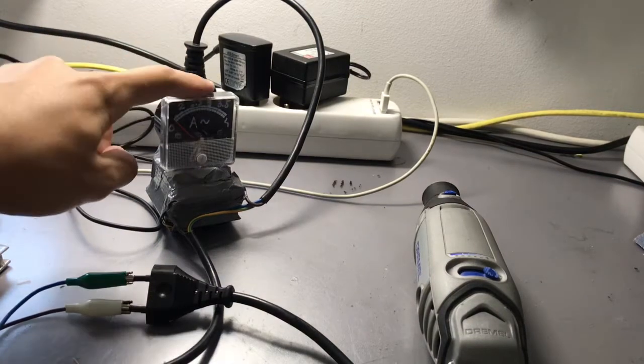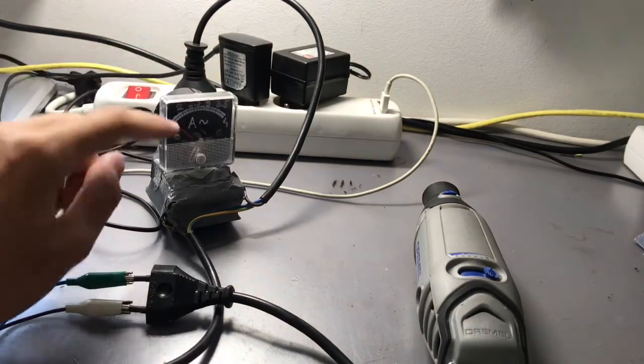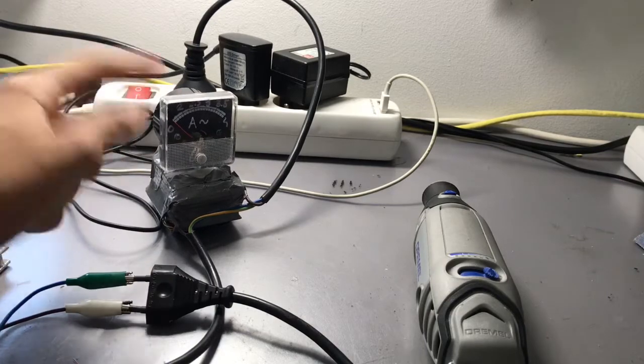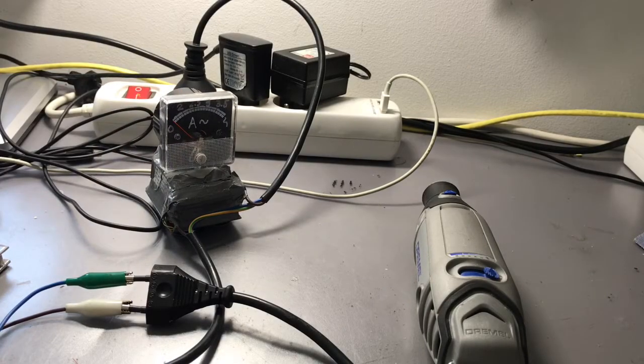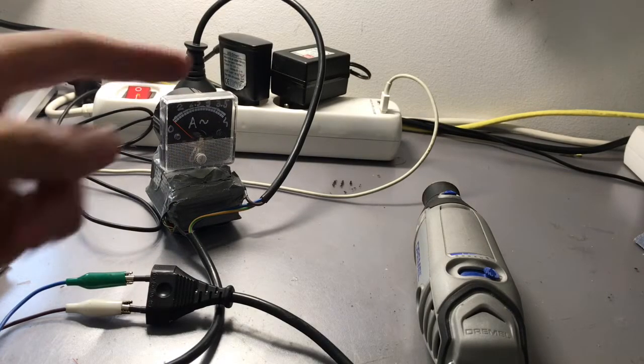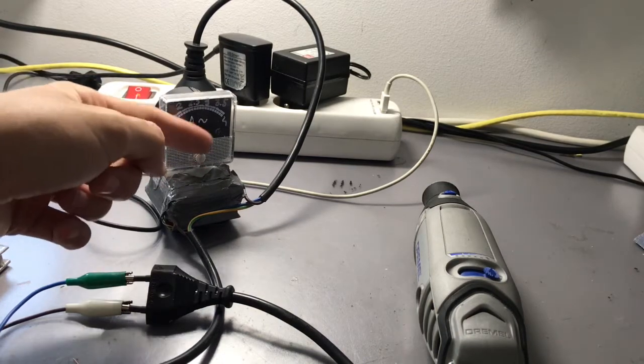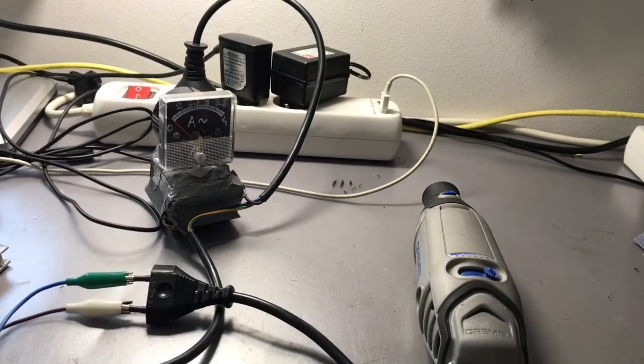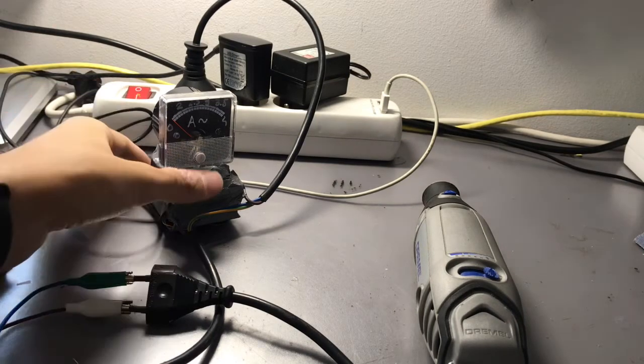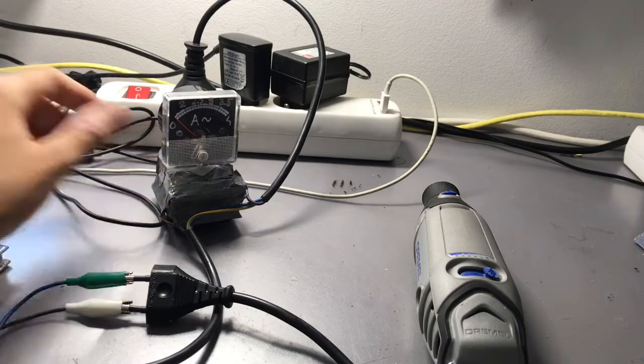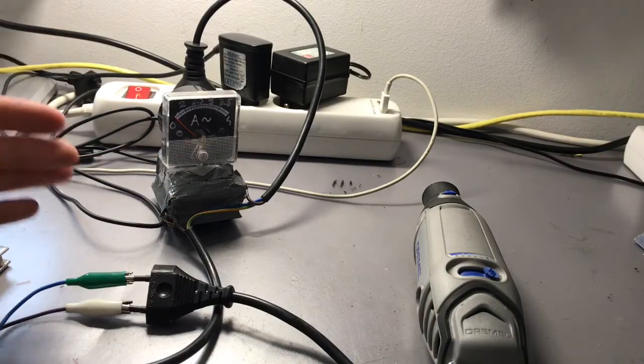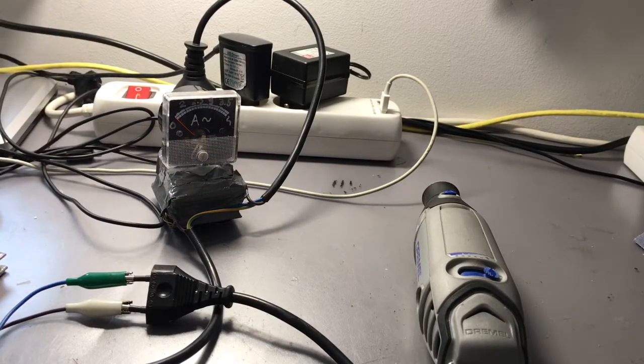If you would want to measure like 1 amp AC, which would be much more precise obviously, you would need a full-scale deflection movement of less than 1 milliamp, or less than 50 microamp full-scale deflection, which will be very, very difficult to get. Nearly any current drawn on the secondary will decrease the voltage, so it's not a circuit for measuring low currents.